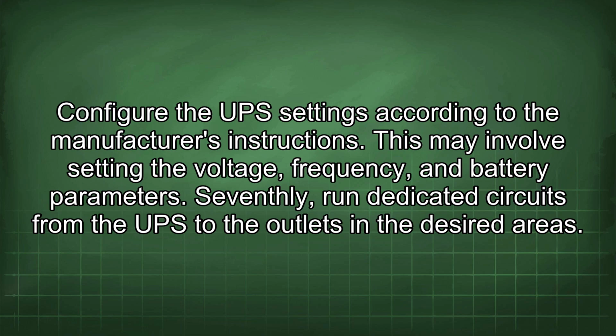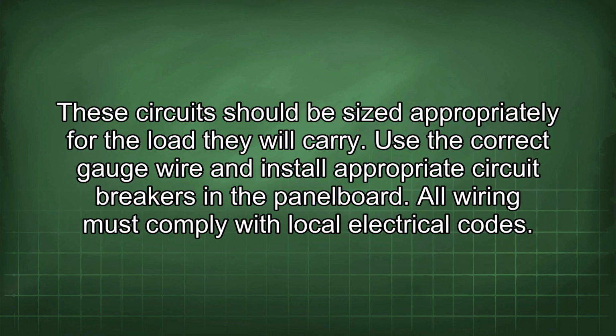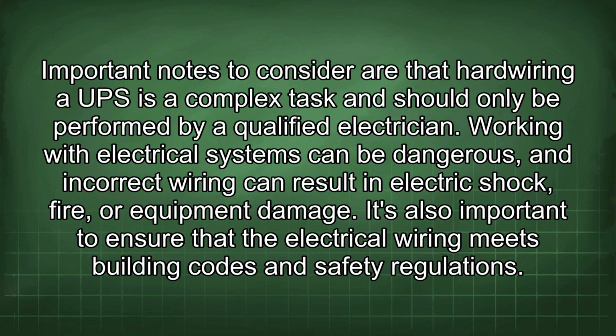Seventhly, run dedicated circuits from the UPS to the outlets in the desired areas. These circuits should be sized appropriately for the load they will carry. Use the correct gauge wire and install appropriate circuit breakers in the panel board. All wiring must comply with local electrical codes. Important notes to consider are that hardwiring a UPS is a complex task and should only be performed by a qualified electrician.